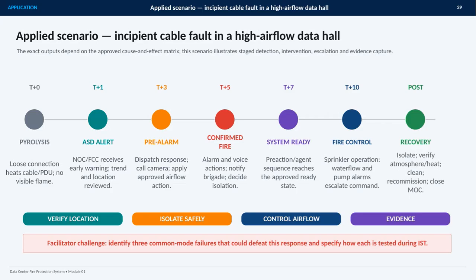This applied scenario follows an incipient cable fault in a high airflow data hall, where a loose connection heats a cable or PDU without producing visible flame. The response is staged, and the exact outputs must always follow the approved cause and effect matrix. At T+1, aspirating smoke detection, or ASD, provides an early warning for the NOC or Fire Command Center to review the trend and location. By T+3, a pre-alarm prompts dispatch, camera verification, and any approved airflow action. If fire is confirmed at T+5, alarm and voice actions begin, the brigade is notified, and isolation is considered.